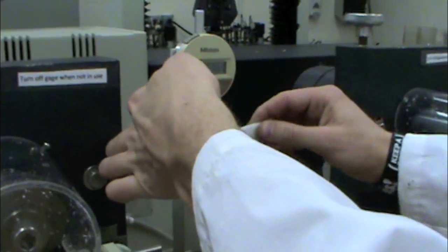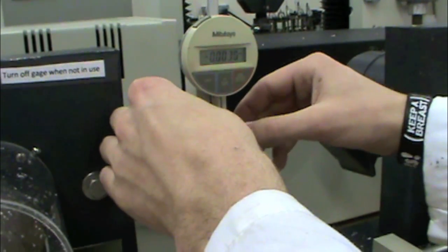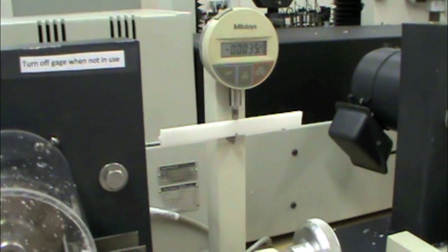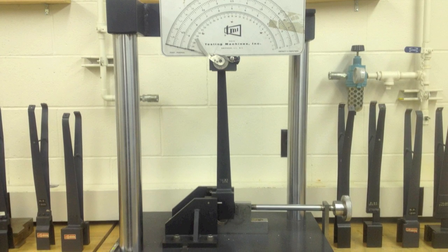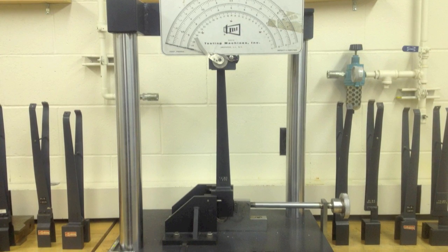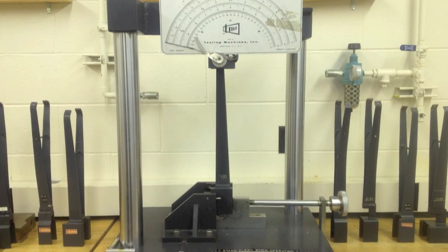Now take the newly notched sample and load it into the V-shaped base of the measuring unit. Make sure that your samples are within 0.010 of an inch tolerance.